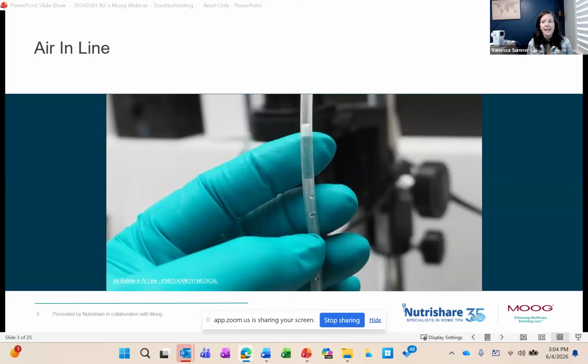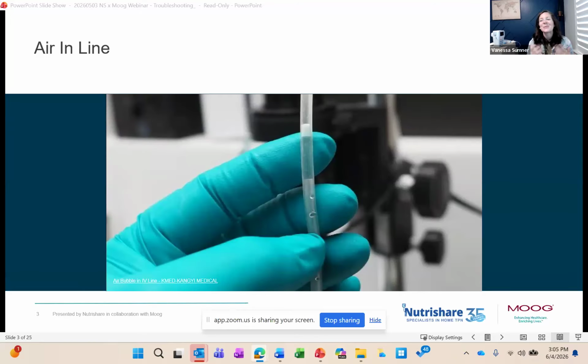There are a couple of reasons air bubbles can accumulate in the tubing, so I'll talk about those and how to troubleshoot them. The first can be from priming the tubing, removing all the air. If you don't do it correctly, this can cause air. Priming the tubing too quickly can cause turbulence. Think of flying in an airplane. What is turbulence? It's basically rough flow. So the fluid moves too quickly through the tubing, causing swirls and friction, and this creates air bubbles.